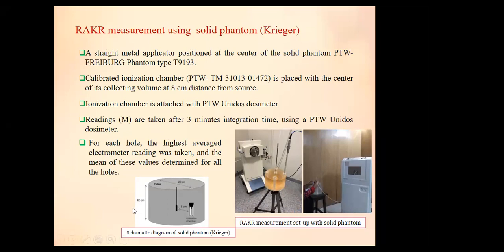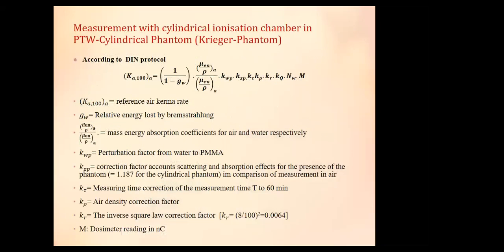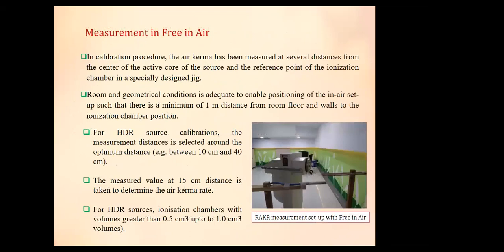For each hole, the average electrometer reading was taken, and the mean of the values was determined for all the holes. The source was made to dwell in a nylon catheter positioned centrally in the phantom. This is the DIN protocol, where the reference air kerma rate is denoted K_A100A. And hence the measurement in air.